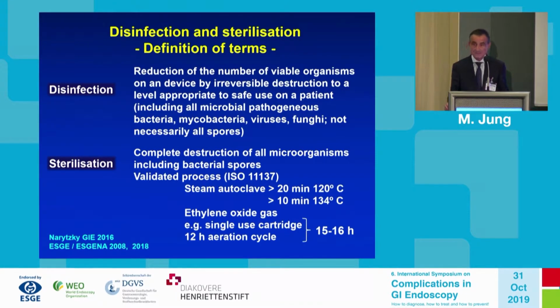Disinfection is defined as the reduction of the number of viable organisms on a device by irreversible destruction to a level appropriate for safe use on a patient. This includes nearly all pathogenic bacteria, but not necessarily all spores. In contrast, sterilization means complete destruction of all microorganisms, including bacterial spores, and it has to undergo a validated process, which is defined by the ISO 11137. Usually, the method used is steam autoclaving, but this is not possible for endoscopes, because it would damage our instruments completely. So what can be offered as a sterilizing process could be a low-temperature sterilizing agent like ethylene oxide gas, but we will see this poses other problems too.